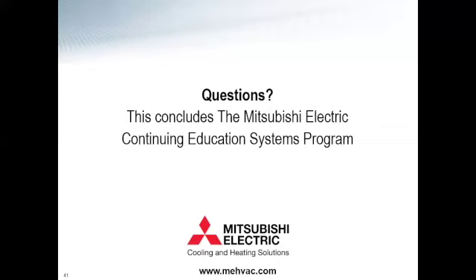Yep. And one thing I should have mentioned earlier is, when you're looking at a passive house application, take into account the heat recovery system. Not only is it more efficient, but it will allow you to shut off your unit. If a unit is not required to provide any heating in a space, you can 100% close down that unit so you're not getting any bleed-through heat. Often in these passive house applications, the bleed-through heat is enough to heat the space because the package is so well insulated. So it's always something important to remember: if possible with a passive house, go with the heat recovery rather than a heat pump.